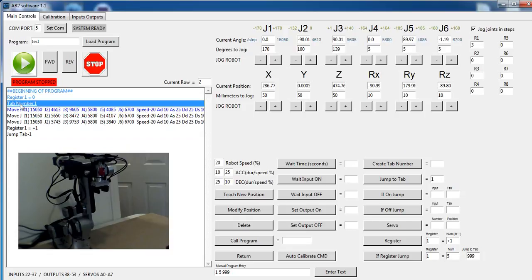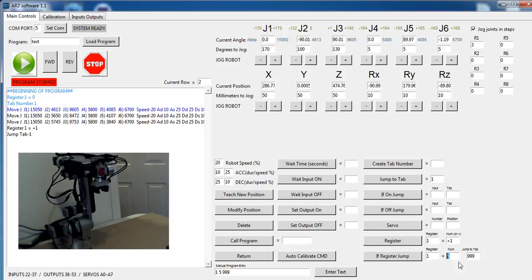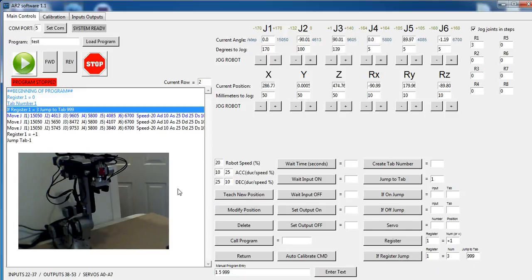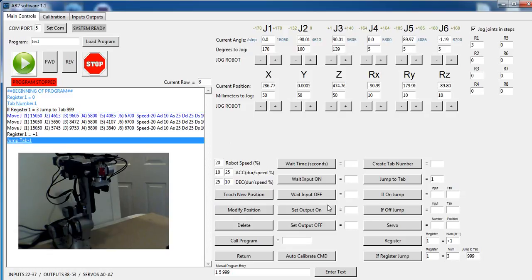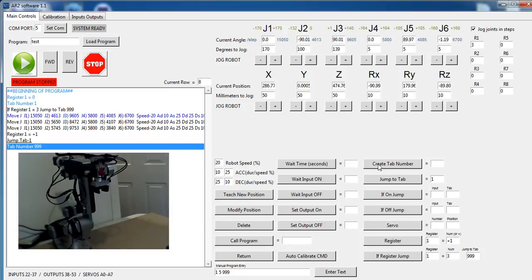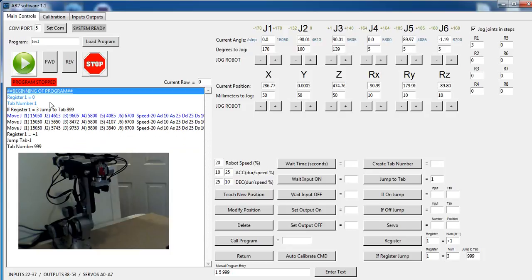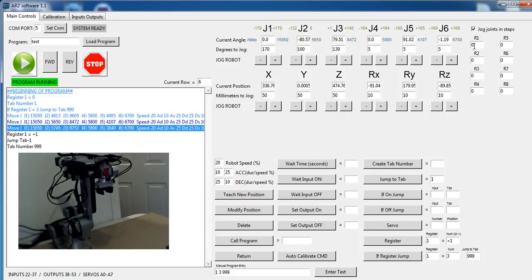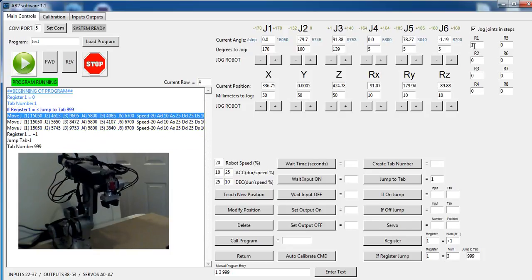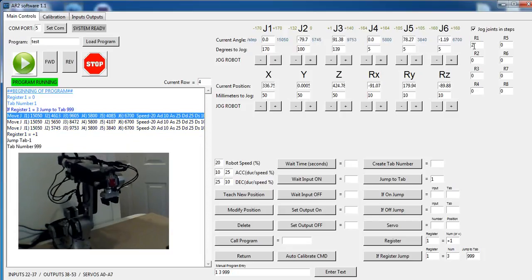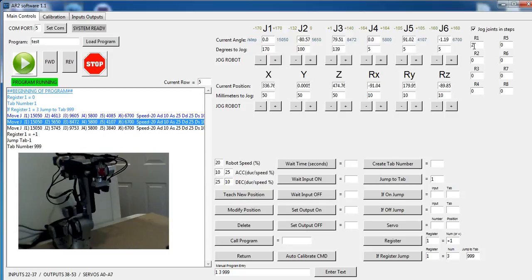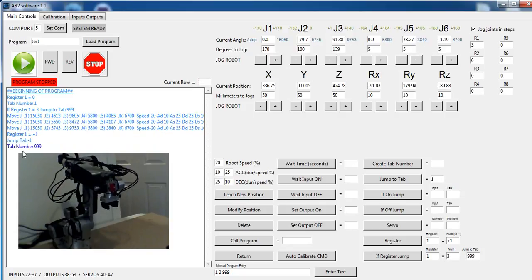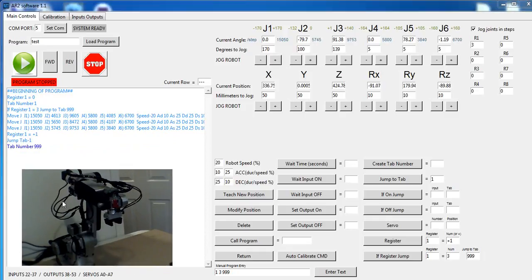So now let's say I only want it to run three times before it stops, and I need a way out. So right after it comes back up here to tab number one, I'm going to give it a way out. So I'm going to tell that if, let's say if register one equals three, then I'm going to jump to tab nine nine nine. That'll be the end of my program. So I've put these values in here. I'll click on that. I'll put this right below that line. But I don't have a tab nine nine nine yet. I need to put that at the bottom. So now, when I start my program at the beginning, it's going to zero it out, and then it's going to run it to three times. And when this gets to three, it hits the end, and the program stopped. It only ran it three times. So that's how I can control the number of times I want a program to run.